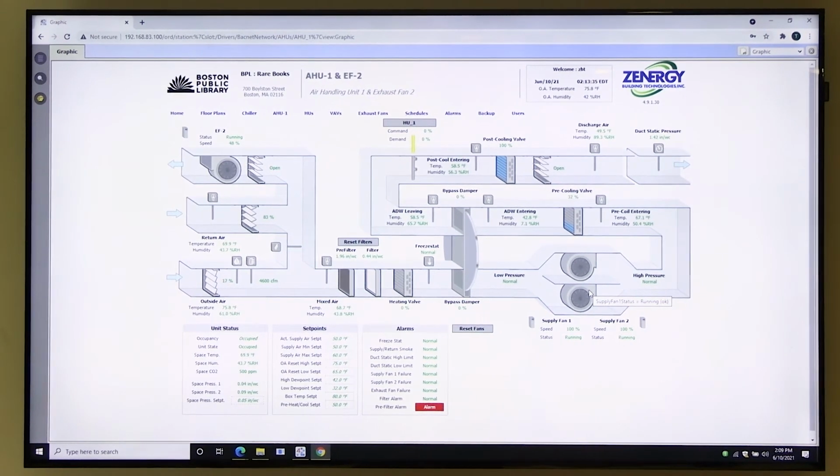So what were the design sequences or set points, and how granular was that information that you guys built this off of? It gets pretty specific. I'm going to walk through each. A VAV box is pretty cut and paste. The VAV in this building is going to be the same as the VAV in that building. This air handler is pretty unique. I've never seen any air handler like this, honestly. So the sequence provided for this air handler is very specific. Each piece of equipment is doing a very specific thing. If that answers your question.